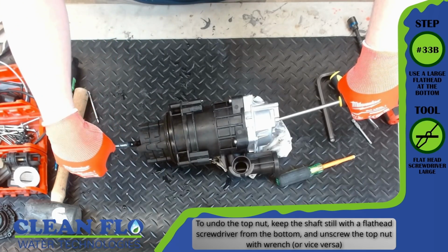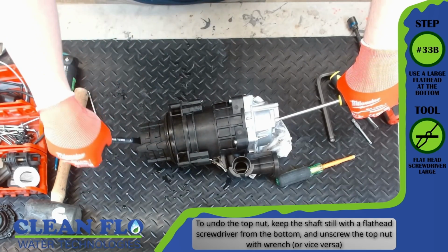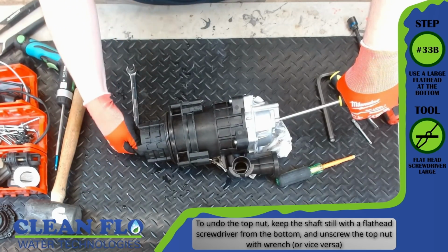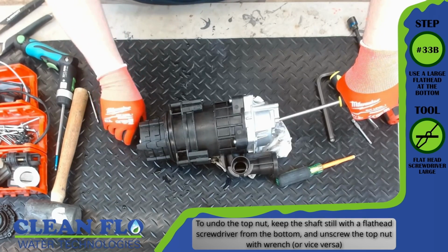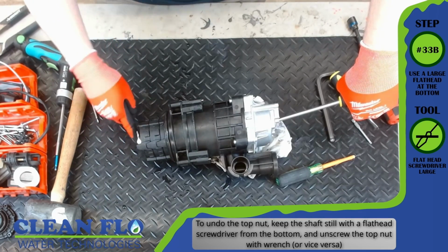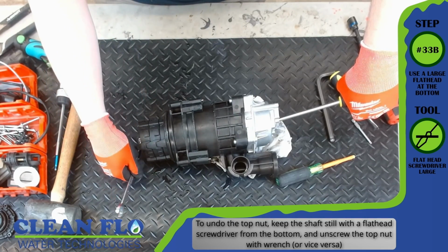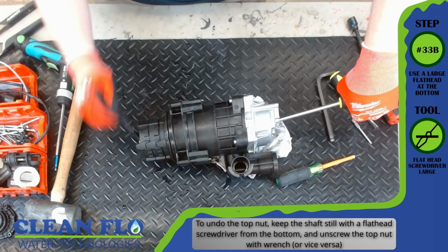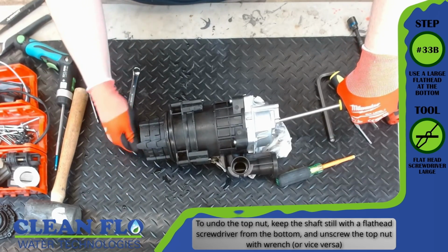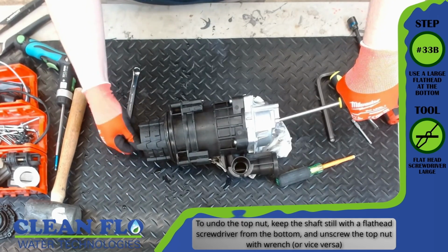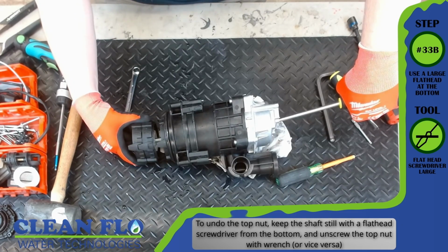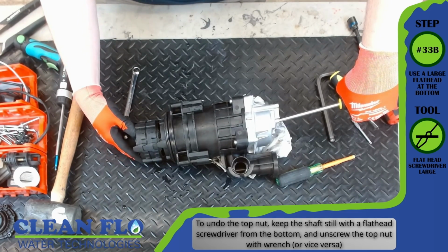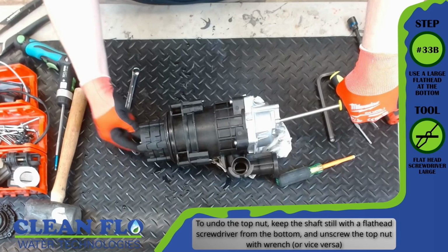Number 33B, use a large flathead screwdriver at the bottom. Tool, flathead screwdriver. To undo the top nut, keep the shaft still with a flathead screwdriver from the bottom and unscrew the top nut with a wrench, or vice versa. Once you remove the nut off the top and the washer, the pump stages will easily slide off.